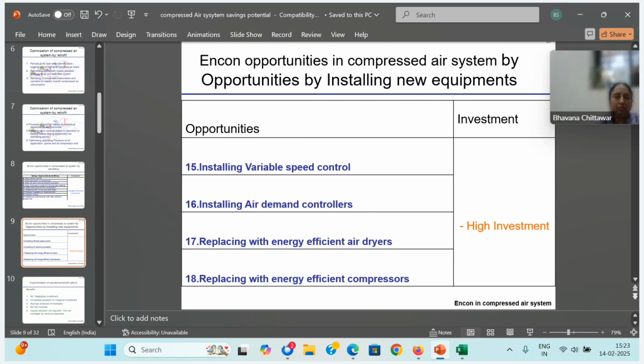In a lot of equipment, by replacing with lower size, innovative equipment, you will save power. So you have to study properly, for your application, your capacity, your pressure, what is the best suited equipment. It may be a little inefficient, volumetric efficiency is less, but your power consumption will be low. So you have to select suitably, very smartly.